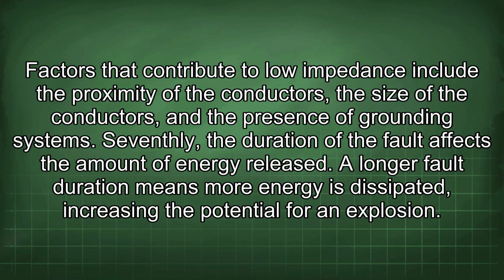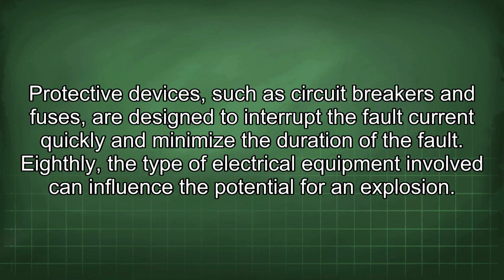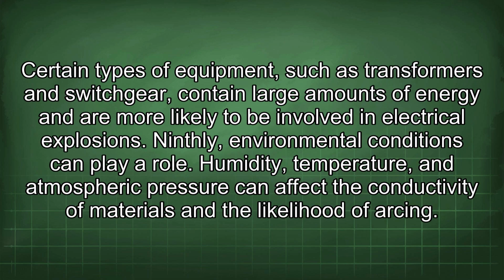A longer fault duration means more energy is dissipated, increasing the potential for an explosion. Protective devices, such as circuit breakers and fuses, are designed to interrupt the fault current quickly and minimize the duration of the fault. Eighthly, the type of electrical equipment involved can influence the potential for an explosion. Certain types of equipment, such as transformers and switchgear, contain large amounts of energy and are more likely to be involved in electrical explosions. Ninthly, environmental conditions can play a role.